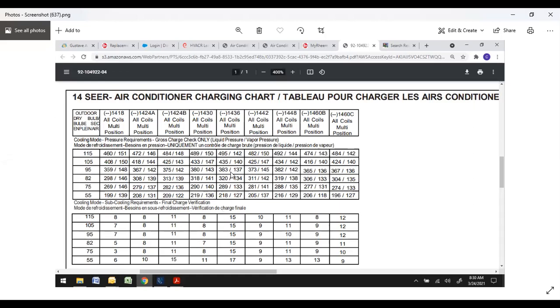And don't keep charging until you get to that point and trying to achieve that. Once you get to the ballpark pressures you're looking for, then you'll come down here and check your subcooling. If you're high on your subcooling, you've got too much. If you're low on your subcooling, slightly add, let it circulate, let it stabilize until you reach, in this case here, 15 required, gets you to about a 13. 13 to 15, you'll be perfect.